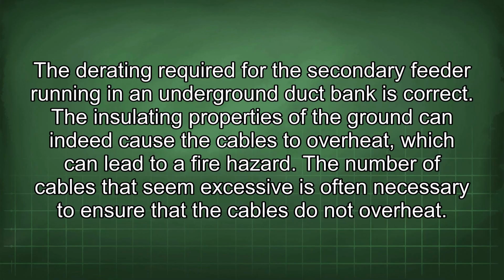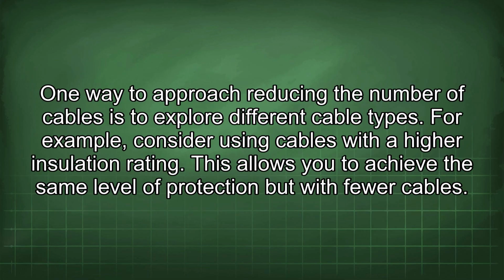The derating required for the secondary feeder running in an underground duct bank is correct. The insulating properties of the ground can indeed cause the cables to overheat, which can lead to a fire hazard. The number of cables that seem excessive is often necessary to ensure that the cables do not overheat. One way to approach reducing the number of cables is to explore different cable types. For example, consider using cables with a higher insulation rating. This allows you to achieve the same level of protection, but with fewer cables.